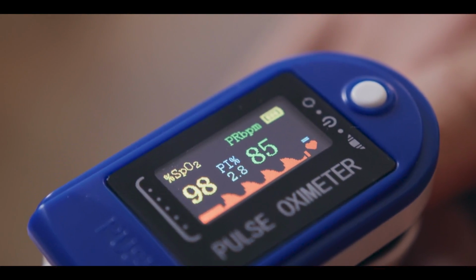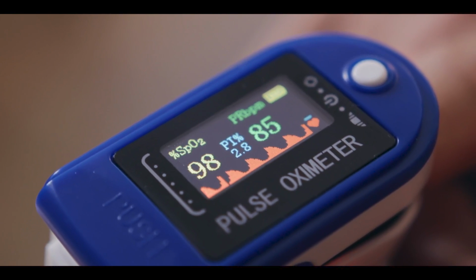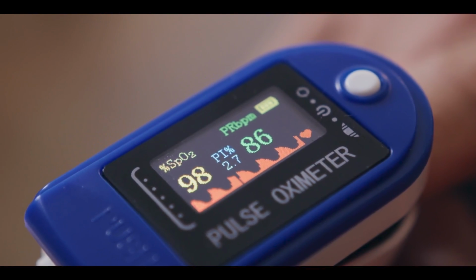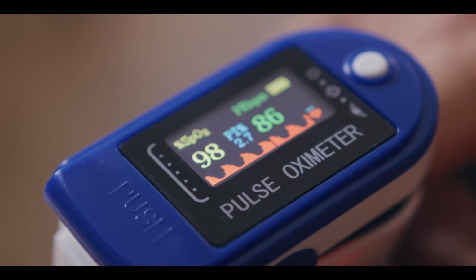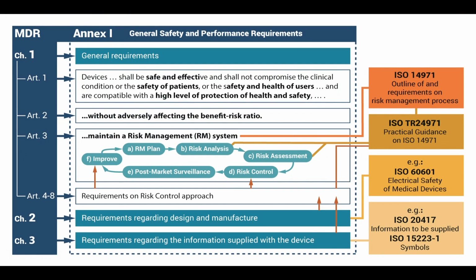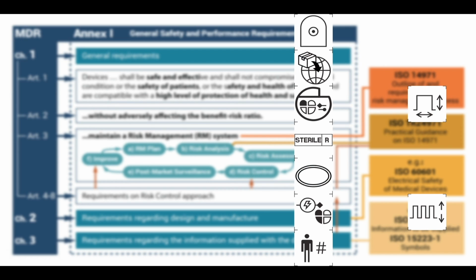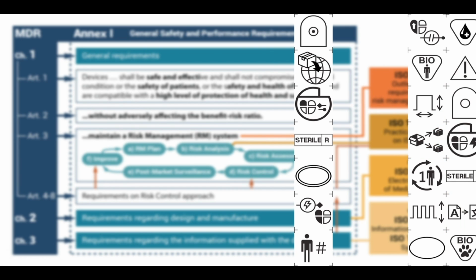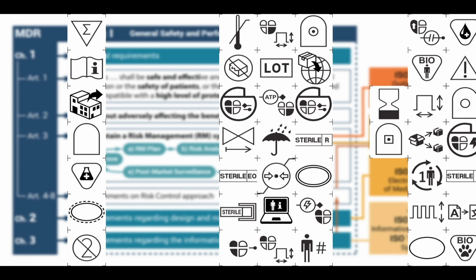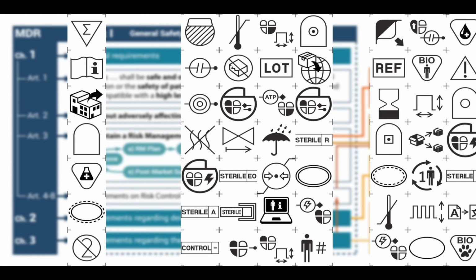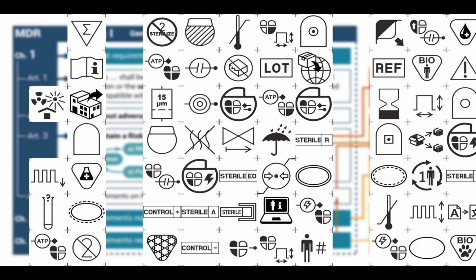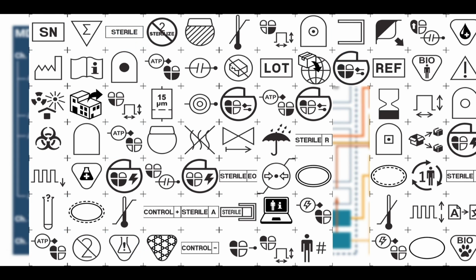And did you ever wonder how it's possible that so many symbols in user manuals, on devices, and even on the packaging of devices are so much alike? Well, we have ISO 15223-1 to thank for that. Because that's not just a document full of text, but it comes with an online database with bitmap and vector images of almost any symbol that could be used on a medical device. This is a great set of images to use for your medical device hardware or software interfaces, because these symbols have been tested with all kinds of users and are standardized.